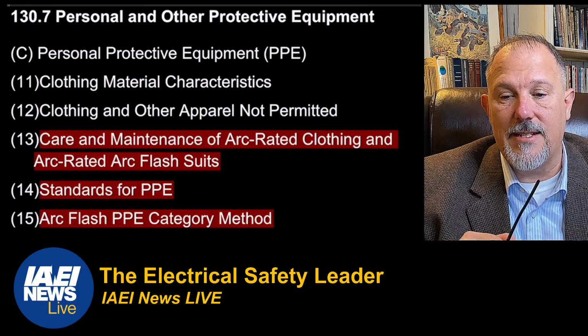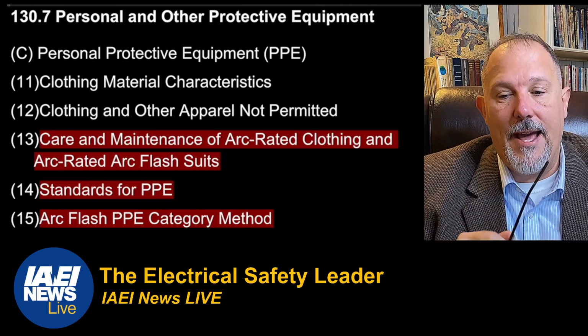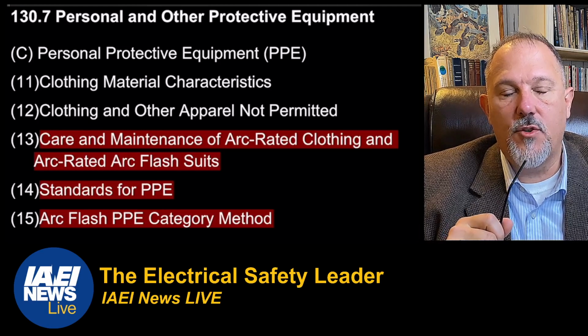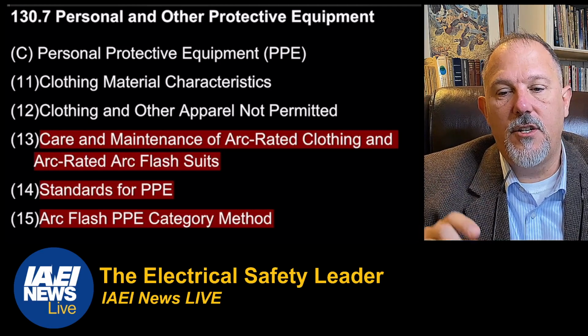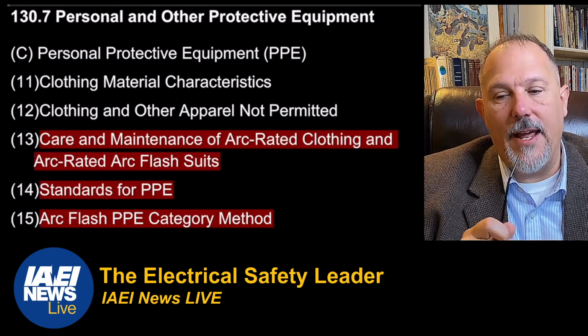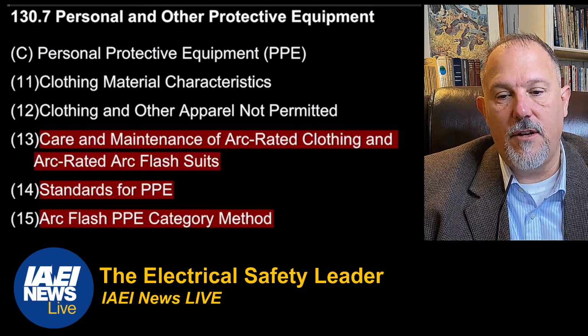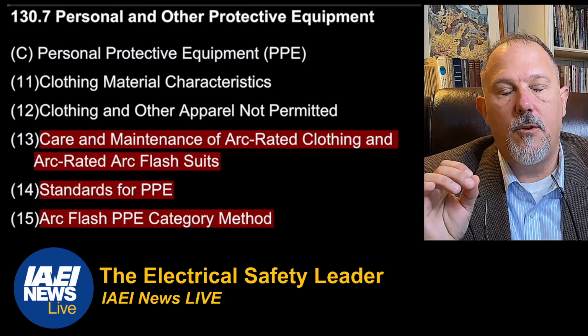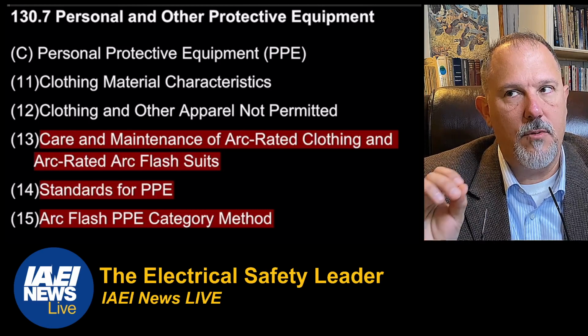This is that new standard, ASTM. They made some modifications to the informational notes to align with the style manual, but they added ASTM F3258, which was published in 2021, recognizing non-leather protectors for rubber gloves to correlate with the global revisions made on this topic. So the title of ASTM F3258 is the standard specification for protectors for rubber insulating gloves meeting specific performance requirements. So the bottom line is they may not be leather. So we can't call them leather protectors.